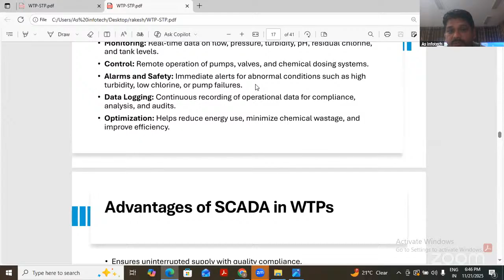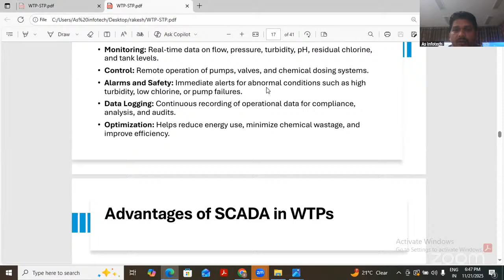Alarm and safety features immediately alert for abnormal conditions such as high turbidity, low chlorine, or pump failure. SCADA also shows pump temperatures, so we can see in this room if pump temperature is increasing, indicating wear and tear, mechanical problems, or ventilation issues, especially in summer. We can easily solve these problems with the help of SCADA because it informs us in real time.